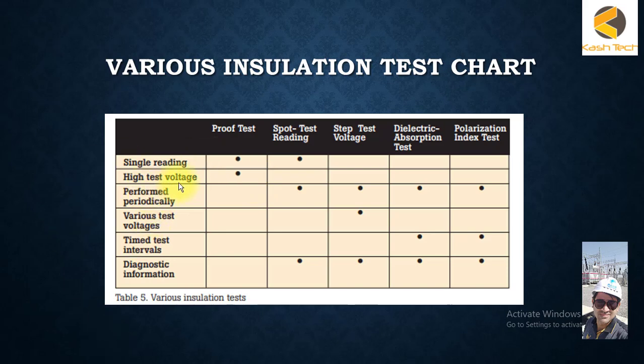The high voltage test is done only during the installation phase — it is not performed during maintenance, so it is not selected for maintenance columns. Periodic testing refers to scheduled intervals such as three-monthly, six-monthly, or yearly, as defined by the regulatory authority or manufacturer.